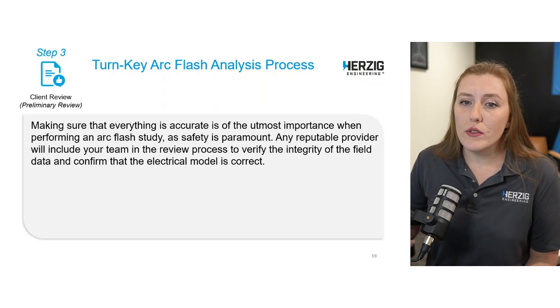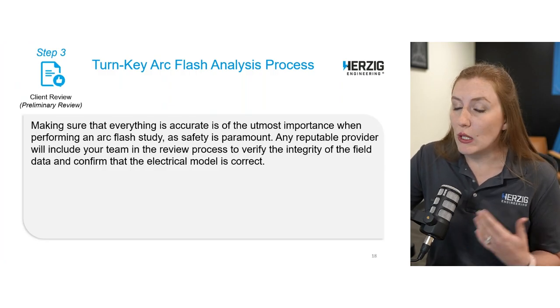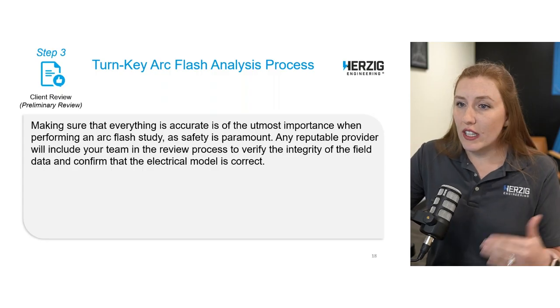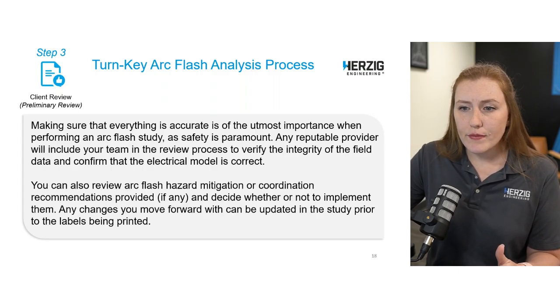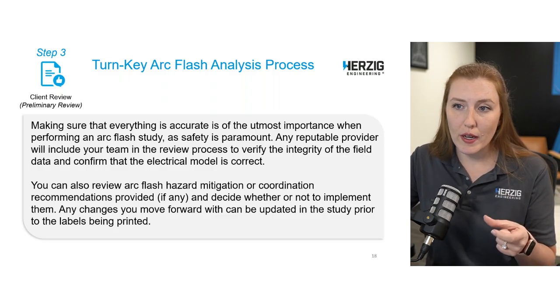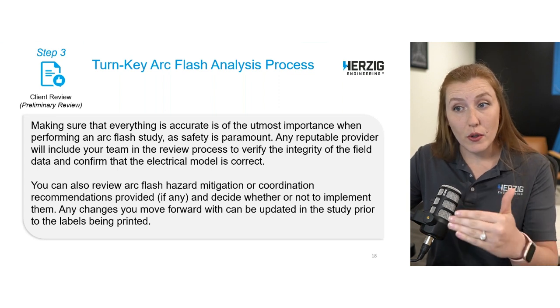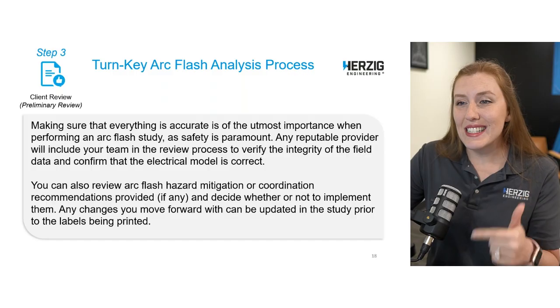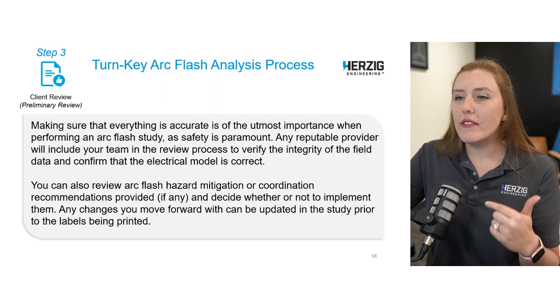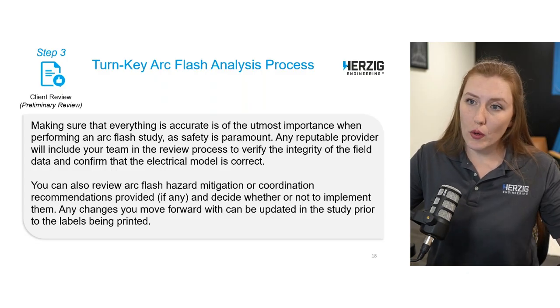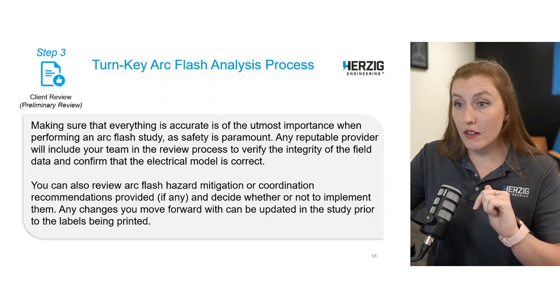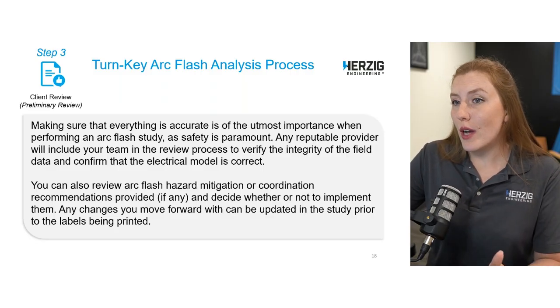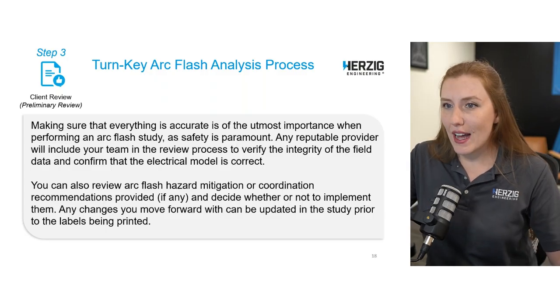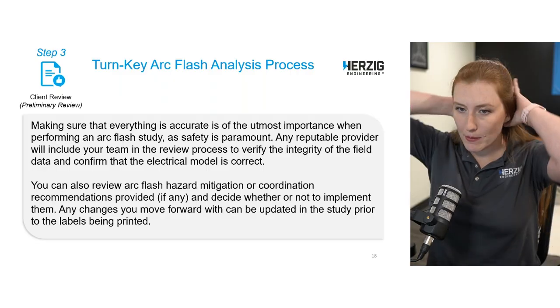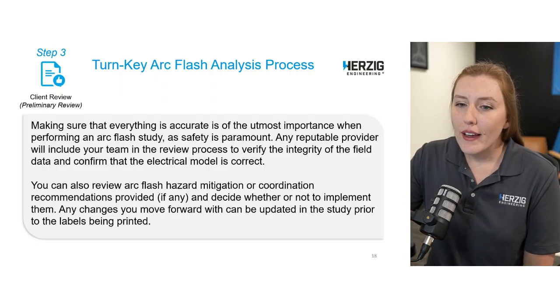All right, so once that is compiled into an engineering report for you, we'll send it over for client review, making sure that nothing's changed from the time the data was collected to now. We'll verify anything that might need double checking. There's also a chance at this step to look over those recommendations, the mitigation to lower the hazards or the protective device coordination to make sure it's all tripping in order, and decide if you're going to implement those recommendations. So you'll be given an opportunity to accept or put on hold any of those recommendations. If you accept it, if you confirm that it's going to happen, we'll move forward updating the study accordingly and printing labels with the lower hazard ratings. We have to get confirmation though. We're not going to assume that you swapped out a breaker setting or a fuse type. We need confirmation, right?